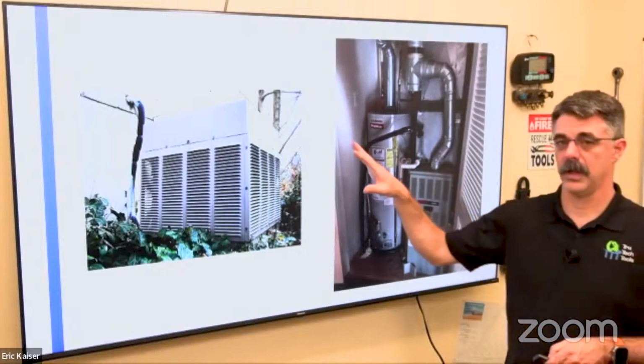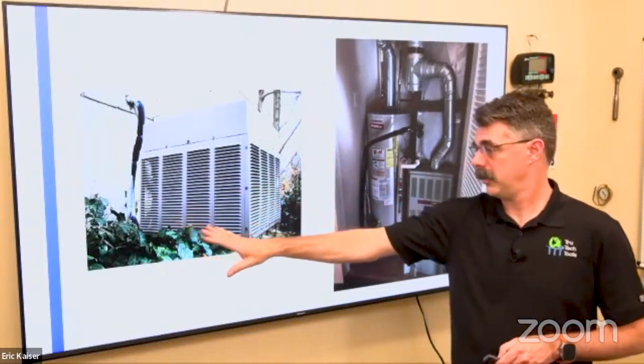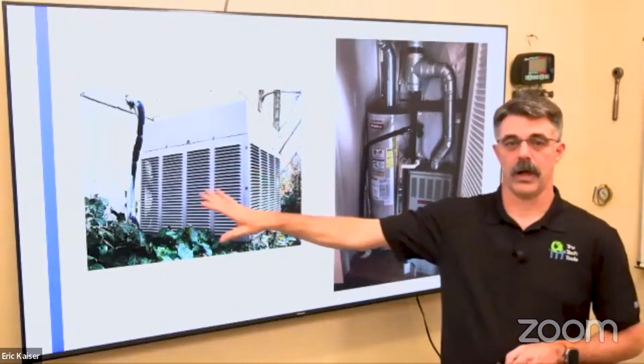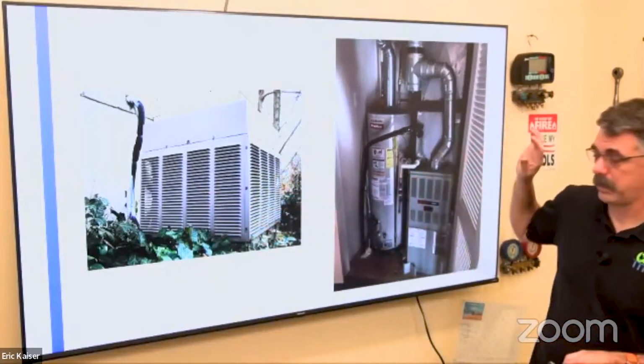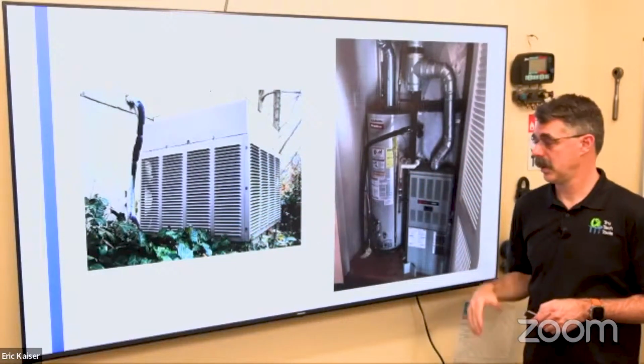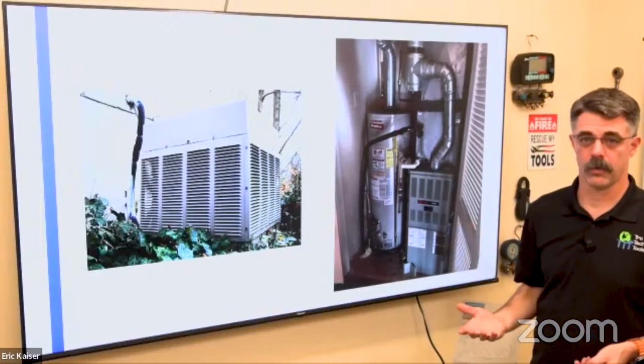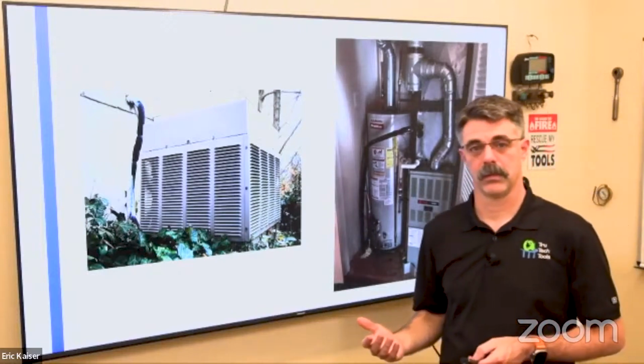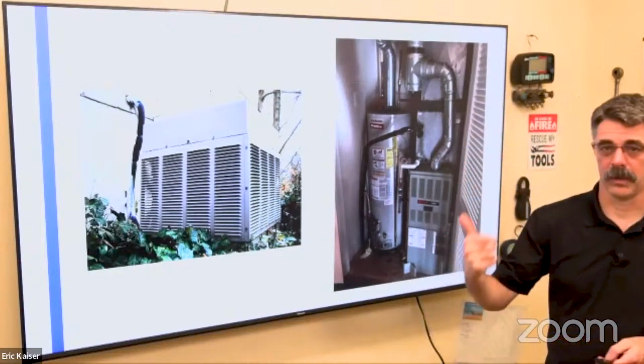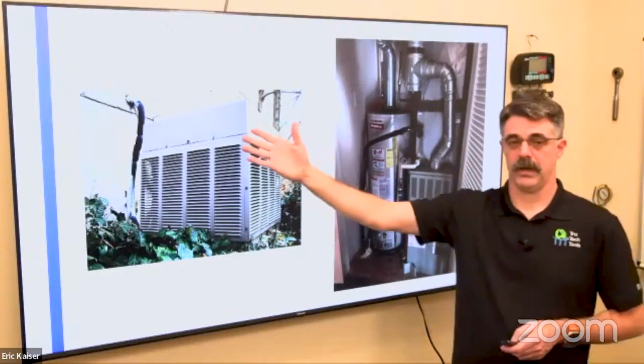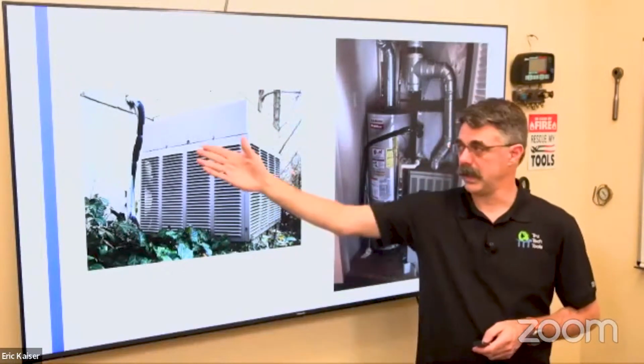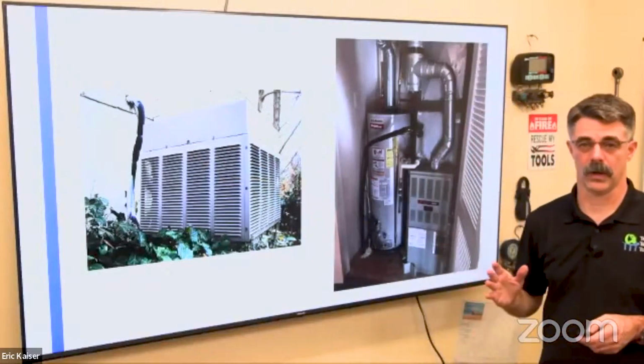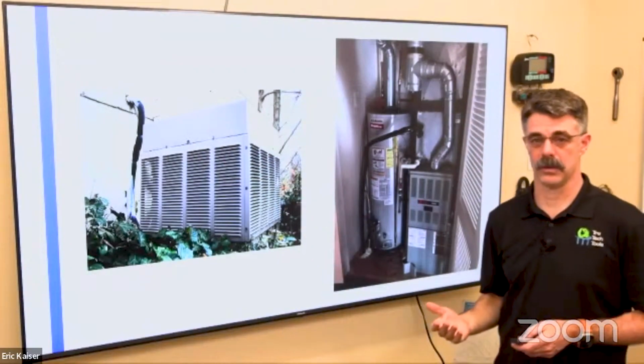Installation location, things around the unit. Do we have things that are growing up around the unit? Is there physical space to put the units in place? What about maintenance? All things we've got to look at. Okay. Do we need to replace wiring? Do we have to put in different disconnects, run new refrigerant lines? All these things we've got to look at when we're looking at the location of equipment.